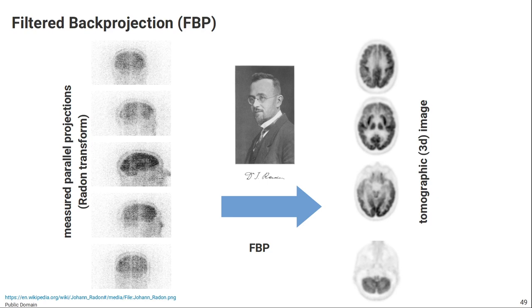But if you look at all modern PET and SPECT scanners, none of those scanners is using FBP as the default reconstruction method, and that has several reasons. One reason is that FBP doesn't handle the noise on the data that we acquire in nuclear medicine very well. A second reason is that in FBP you assume that the measured data is the exact line integral of your object, and as we will see in one of the following videos, this is not exactly true for PET and SPECT imaging — the line integral is a reasonable approximation, but it's a bit more complicated.